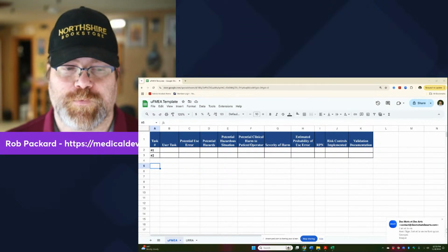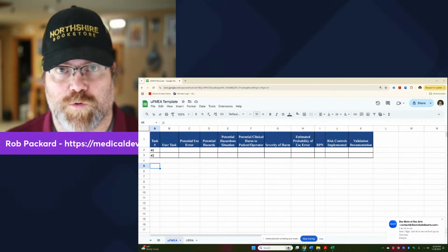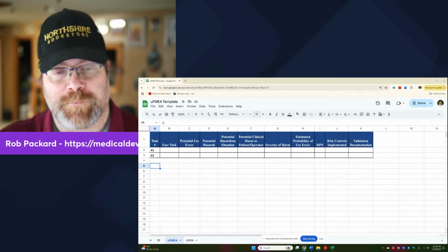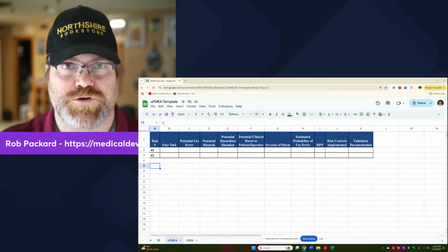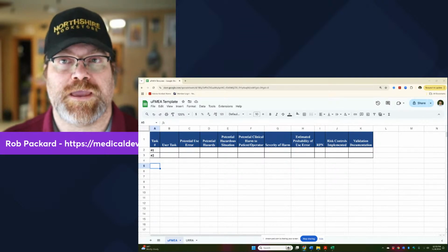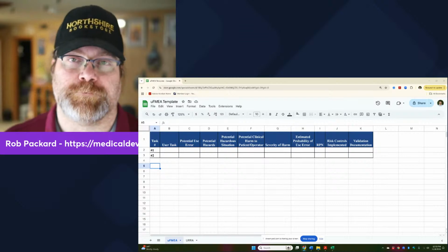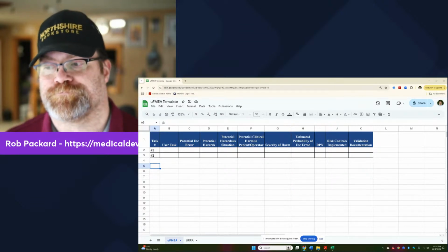And then the next item we have on here is potential clinical harm to the patient or the operator of the device. So if you use an infrared thermometer incorrectly, it's very unlikely you're going to hurt the user, but it is possible that you might create a hazardous situation because you incorrectly measure the temperature. So instead of treating them for a fever, you might say, oh, your temperature is normal. But in fact, you just measured the temperature incorrectly.